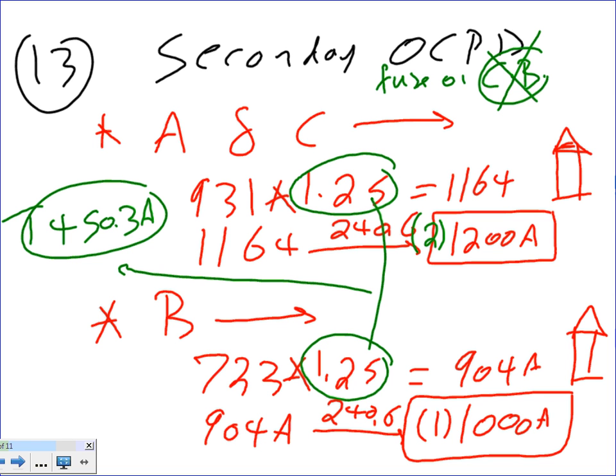Can you do it with circuit breakers? You don't. The circuit breakers are either 1000 or 1200. And by the way, if you went with 1200, you exceeded what the code requires. Say I decided to go 1200 amp on every phase, you exceeded what the recommendation on phase B would be. I know it's goofy, but the good news is, guys, 95% of the time all the phases are the same, so you don't get into this situation.